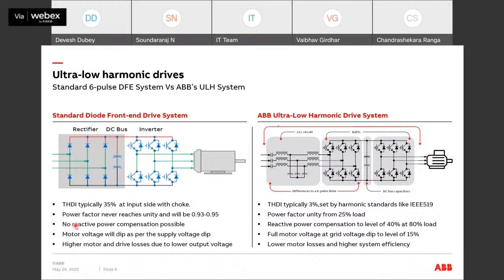What is the basic difference in both technologies? Any VFD will have three portions. First is the rectifier, also called a converter. It will have a DC bus, and then the inverter comes. The same is in active front-end drives also: we have a rectifier, a DC bus, then an inverter. The difference comes in the topology. When the rectifier section is diode based, it becomes a diode front-end drive. When this rectifier or converter is replaced with IGBTs, the system becomes an active front-end solution.